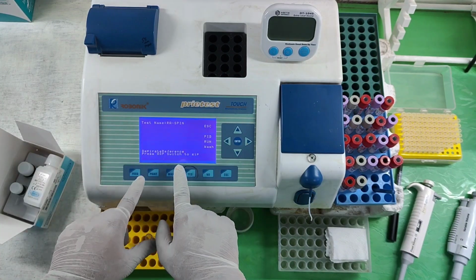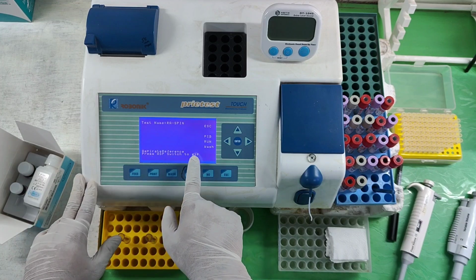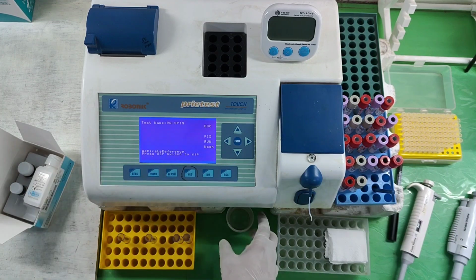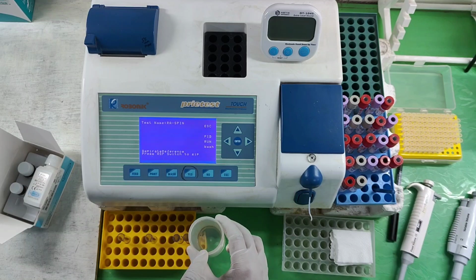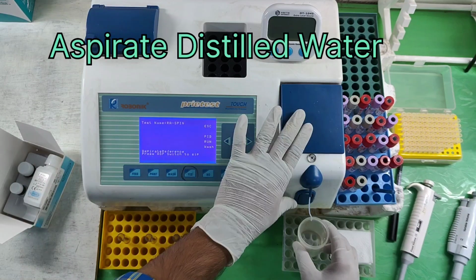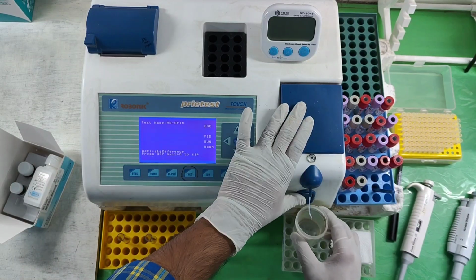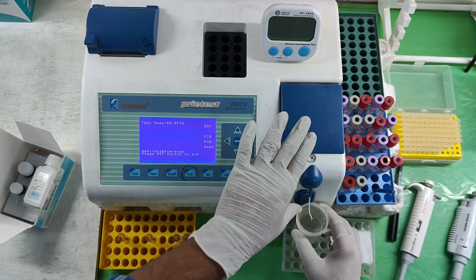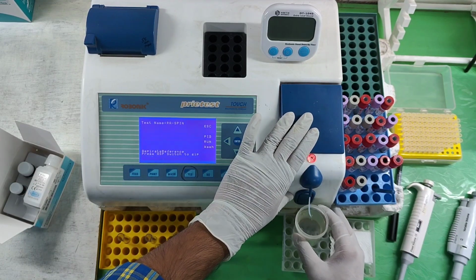Now look at the machine. Here it's showing aspirate reference. For this, I am going to aspirate distilled water or deionized water. This is the aspirate switch. I am going to place this and push this button.